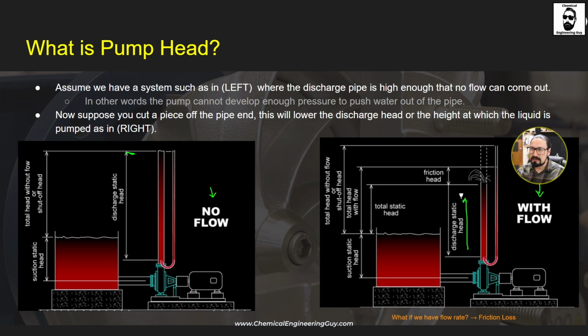The most important part, and the one I want to focus on, is how we measure the total static head, the total head with flow, and the total head without flow. These are the three main concepts I want to show you. This first one is theoretical - it's not going to happen because we don't have a system with stagnant flow rate.